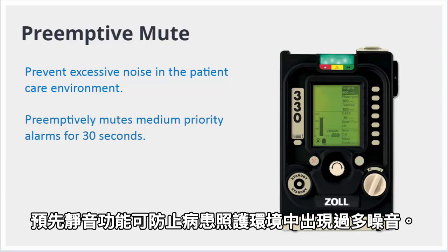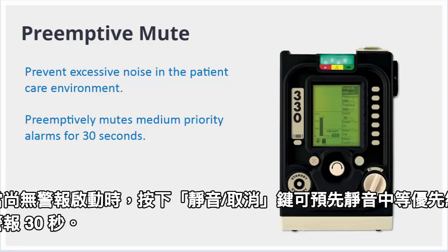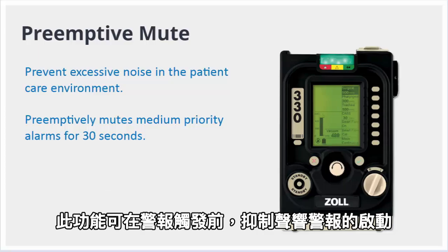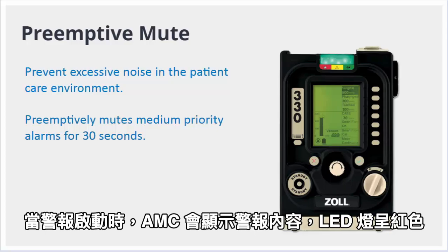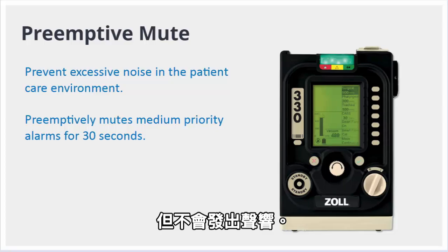Preemptive mute is a means to prevent excessive noise in the patient care environment. When there is no active alarm, pressing the Mute Cancel button preemptively mutes a medium priority alarm for 30 seconds. This enables you to prevent the audible alarm. When the alarm is triggered, the AMC displays the alarm and the LED is red, but there is no audible alarm.